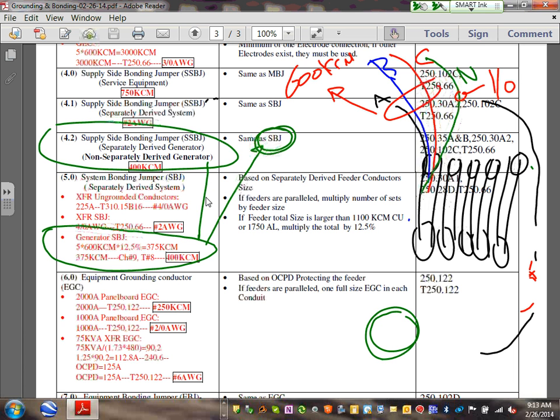The supply side bonding jumper at the generator and the system bonding jumper at the generator are identical, exactly like the main bonding jumper and the supply side bonding jumper at the service. They are always identical. You need to do the calculation? No. So you just say identical and put the number for me. Any comments, guys? Any questions about the supply side bonding jumper at the generator? Adam? Makes sense? Yes? No? A little bit? Confusing? A lot of info? You guys are graduating now. We're going to send you to the good life, right?